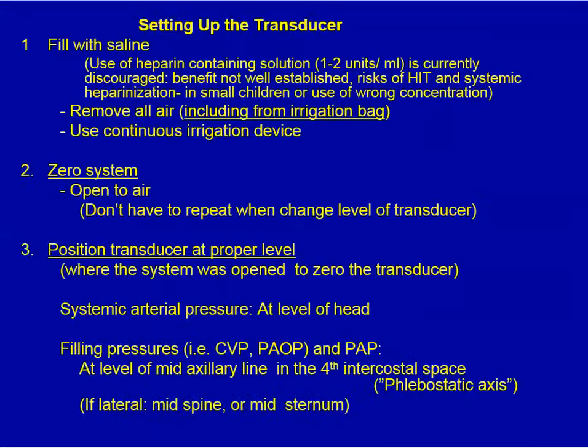A word about setting up the transducer. We're all spoiled because our technicians often do this, but remember, you are ultimately responsible. The most important thing is that the irrigation system and all of the catheters be totally free of air. I have occasionally encountered systems that haven't been washed out, and this could lead to disaster. I also think it's important to make sure there's no air left in the irrigation bag.